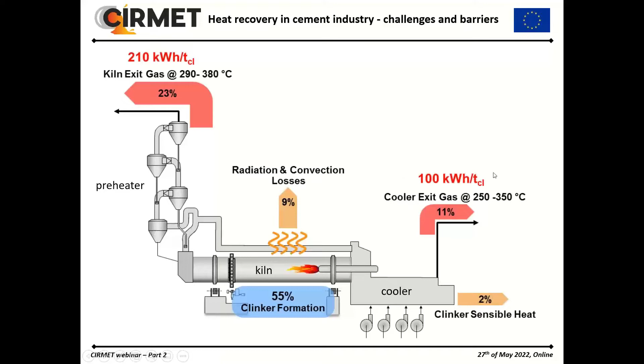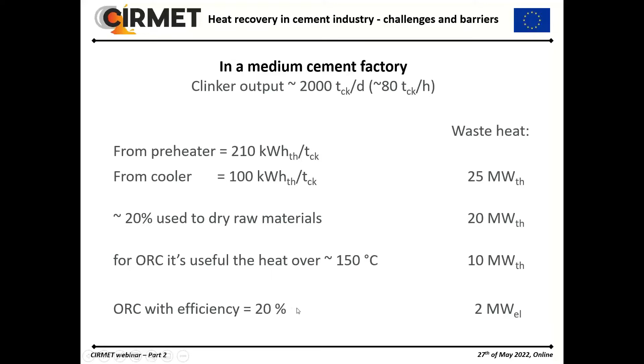So it means a waste heat of about 25 thermal megawatts. 20% of it is used to dry raw material, so the remaining is 20 megawatts. The heat useful for the ORC is over 150 degrees, so it remains about 10 megawatts. With an efficiency of 20%, we obtain 2 electrical megawatts. So with an ORC, we save electricity from the grid, and then we avoid emitting CO2 in the atmosphere to make electricity.